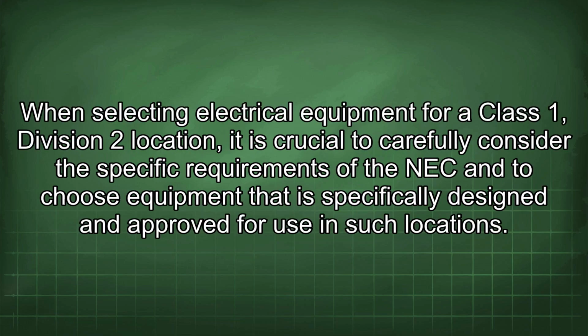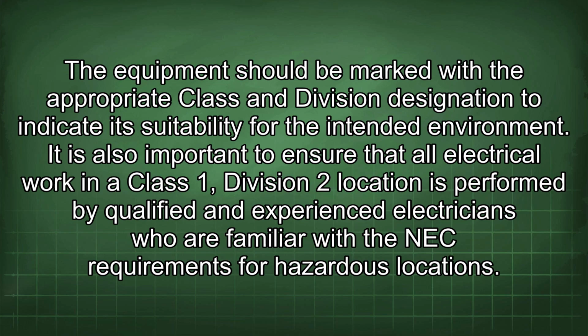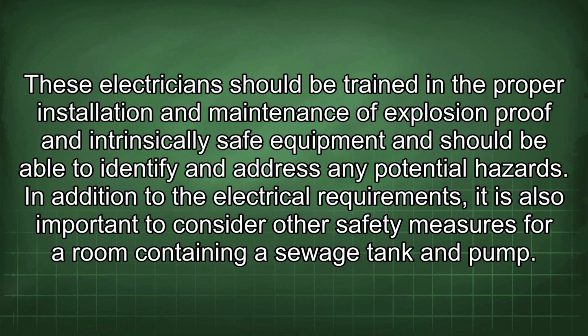When selecting electrical equipment for a Class 1, Division 2 location, it is crucial to carefully consider the specific requirements of the NEC and to choose equipment that is specifically designed and approved for use in such locations. The equipment should be marked with the appropriate class and division designation to indicate its suitability for the intended environment. It is also important to ensure that all electrical work in a Class 1, Division 2 location is performed by qualified and experienced electricians who are familiar with the NEC requirements for hazardous locations. These electricians should be trained in the proper installation and maintenance of explosion-proof and intrinsically safe equipment and should be able to identify and address any potential hazards.